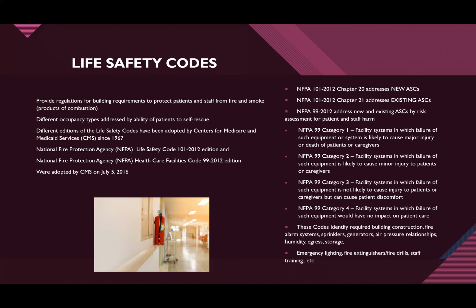But in all cases, and there is no category 4 in ASCs today, but in all categories, somehow you need emergency exit lighting. And so if you don't have a generator that's providing you emergency exit lighting so that you can remove yourself from your building, then you need battery backup lights. And that's where all of those things come in.